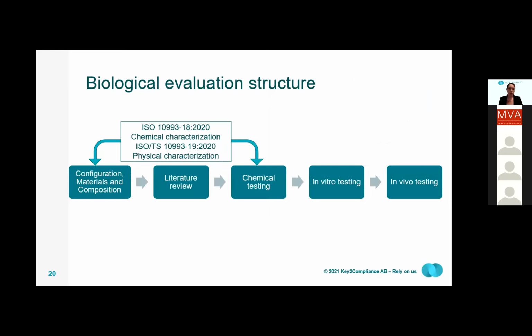So the biological evaluation is a stepwise approach. The very first step is to look at the configuration of the device, to look at the materials in the device, and also down to the detailed composition of the different materials. That would also include, for example, colorants. So this is the step where you review in detail the documentation that you can get from your raw material supplier, for example, material safety data sheets, technical specifications, and various certificates.